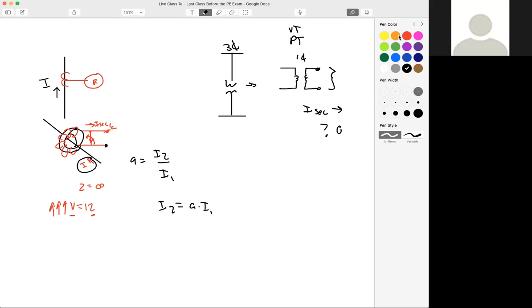If I had a CT right here on this same three-phase system, off to the side, what would my primary current be? It's going to be whatever's on this line for both transformers. And our CT, the way it's built, the secondary current going down is a product of this relationship. So even though it's open, it's still attempting to drive our I2 as a factor of I1.